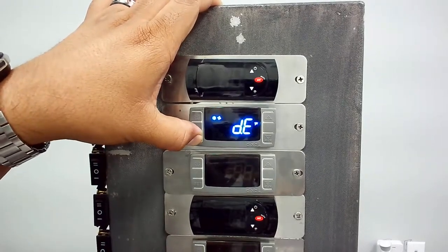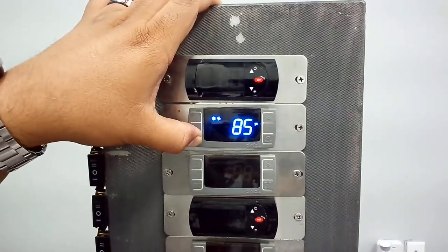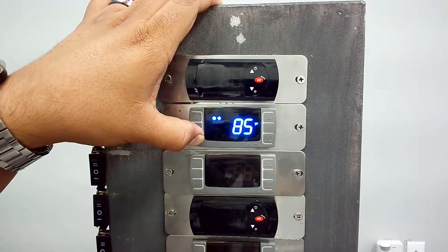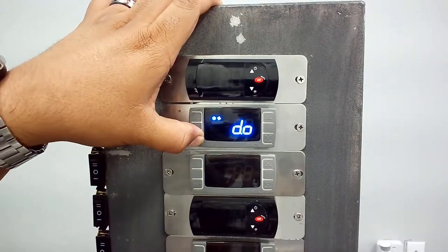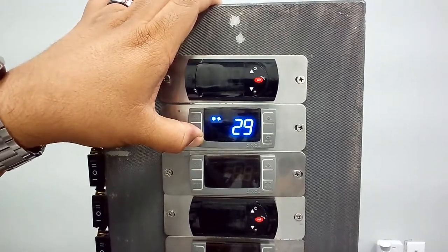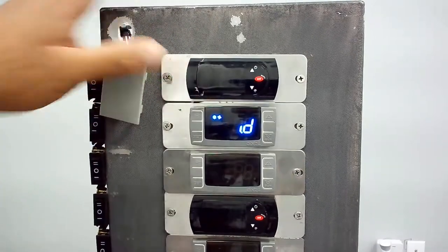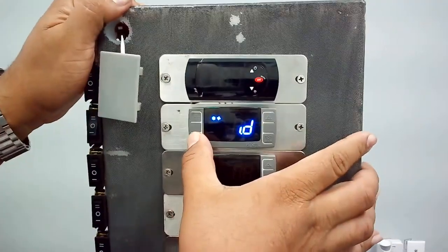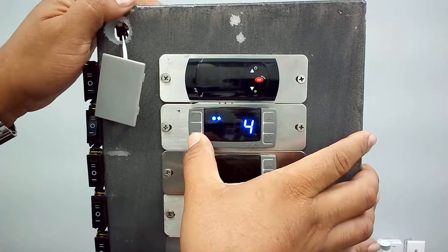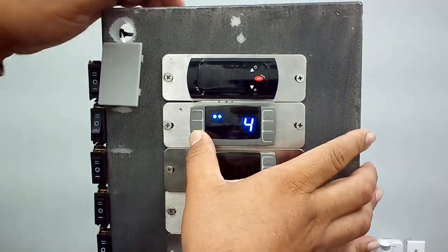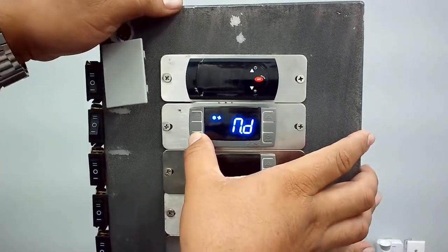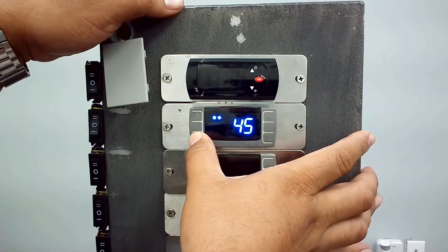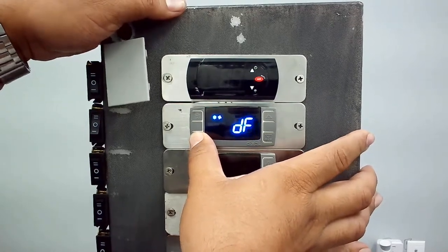DE, this is your defrost termination temperature. That should be set to 85 no matter what unit it is. DO, again, no matter what unit, should be set to 29. nd, this is the length between defrost cycles. That's going to be set to 4 hours for any GR unit. And dF is going to be set to 45 for any GR unit.